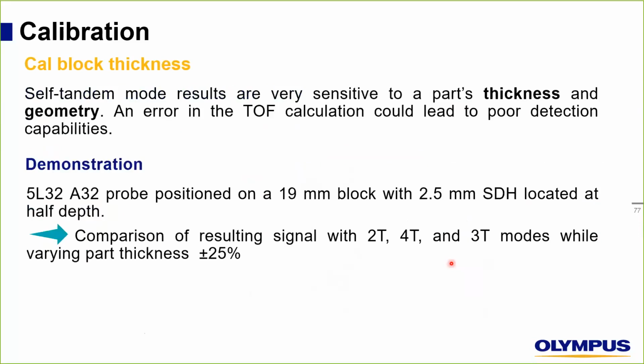self-tandem mode results are very sensitive to a part's thickness and geometry. An error in the time of flight calculation could lead to poor detection capability. So if you are using a different thickness for the calibration block, be very, very careful, especially with the indirect modes. We are talking about 3T, 5T, etc. To demonstrate this issue, we used a 5L32A32 probe positioned on a 19 millimeter block with a 2.5 millimeter SDH located at half depth. We will compare results with 2T, 4T, and 3T modes while varying part thickness by plus or minus 25%.